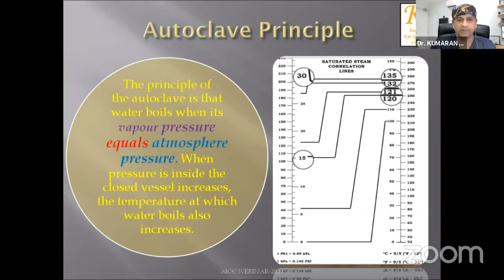The autoclave principle is common to everybody, as we know that water boils when the vapor pressure equals the atmospheric pressure. There are 3 different types of autoclaves which we use in clinical practice, and based upon the type of load which you are going to process, you have to choose. A gravity autoclave is useful for non-porous and non-hollow instruments. The pre-vacuum and the pulse vacuum basically remove the air inside the autoclave to make the steam process more effective.